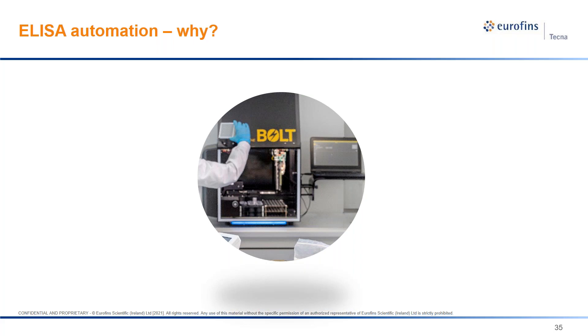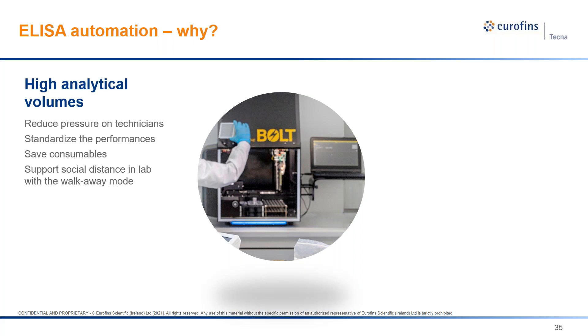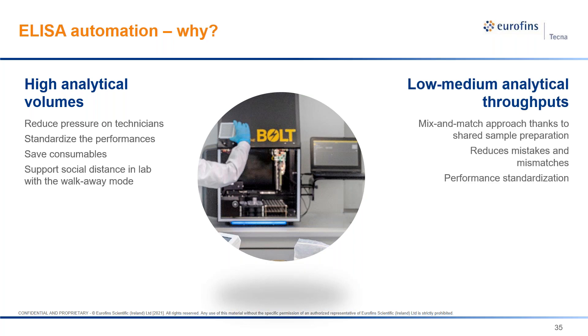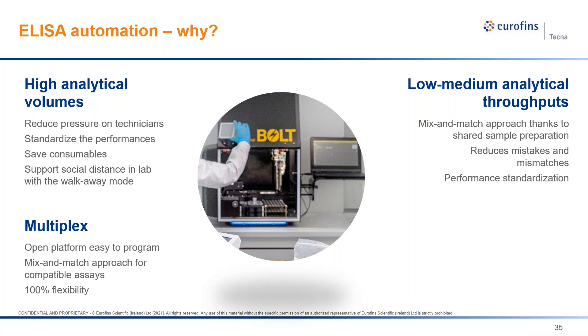Thank you Evelina for the question. If the technician has to run a high number of samples, a robot can reduce the pressure on operators who do not have to perform repetitive manual dispensation. Additionally, the robot is able to run ELISA under standardized conditions and the performance is better than manual analysis — mistakes and mismatches are reduced because the software provides a simple end-user interface. Last but not least, the advantage of a robot is the possibility to run multiplex analysis — the technician can program an analytical session with methods searching for different analytes on the same sample. The automation offers 100% flexibility and the analytical needs of the customer are easily set up.